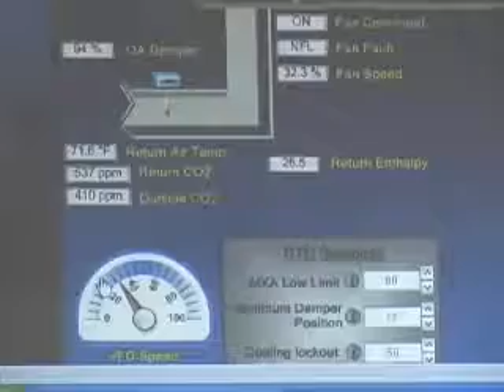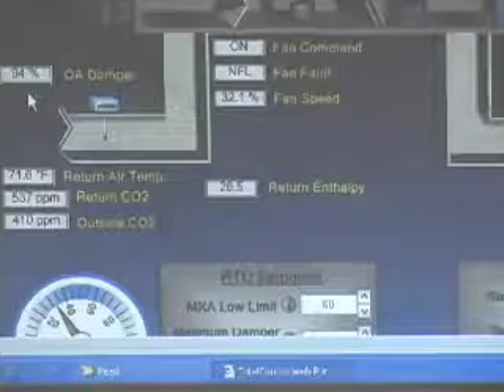idling. The VFD signal is at 32%. So the building is largely satisfied. The rooftop's not doing a whole lot of work, and basically what little work it's doing is with the outside air dampers economizer being open right now. So we're providing 94% outside air, maybe 6% return air, mixing that to get a 64-degree discharge air temp into the space. Believe it or not, a building like this, with a lot of people, computers, and everything else in there, we'll be cooling this building most of the year rather than heating. Some areas may add some heat, and this will really make you feel good about building automation. They're heating this building with electric heat.